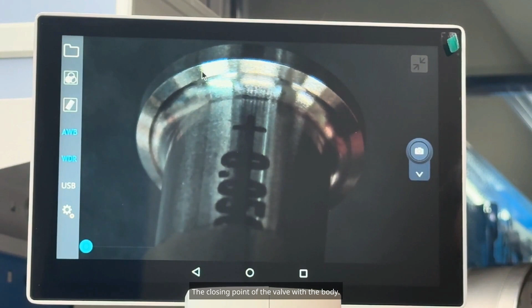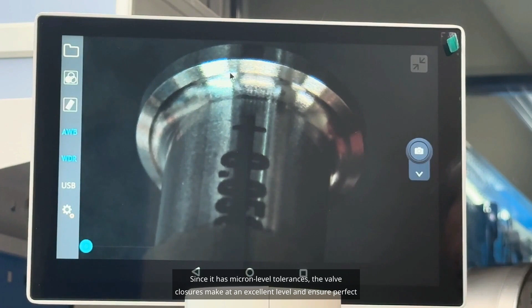When measured for oval deformation, roundness is below 0.5 microns, meaning we achieve values like 0.2 or 0.3 microns. The roundness and lapped surfaces are excellent, and the concentricity, that is, the alignment between the seat and the valve shaft, is 1 micron. Since it has micron-level tolerances, the valve closures are made at an excellent level and ensure perfect sealing with no leakage.